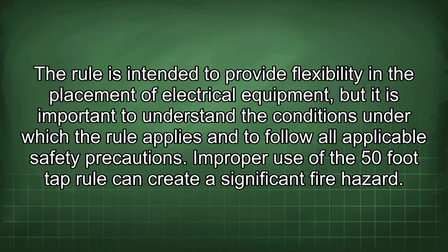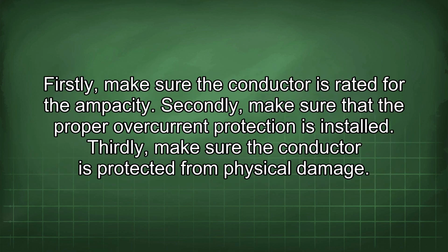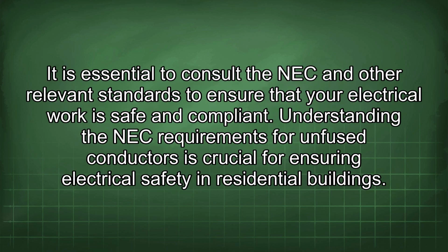The rule is intended to provide flexibility in the placement of electrical equipment, but it is important to understand the conditions under which the rule applies and to follow all applicable safety precautions. Improper use of the 50-foot tap rule can create a significant fire hazard. Firstly, make sure the conductor is rated for the ampacity. Secondly, make sure that the proper overcurrent protection is installed. Thirdly, make sure the conductor is protected from physical damage. It is essential to consult the NEC and other relevant standards to ensure that your electrical work is safe and compliant.